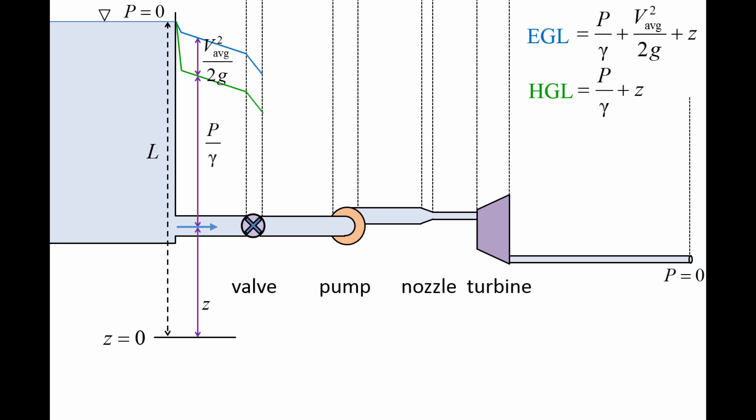Both the EGL and HGL curves drop rapidly at the valve since valves usually induce separated flow, causing a rapid loss in pressure head. After the valve, the EGL and HGL curves continue to decline due to pipe friction.